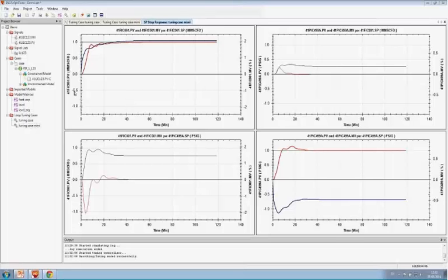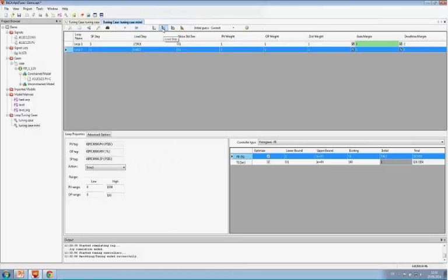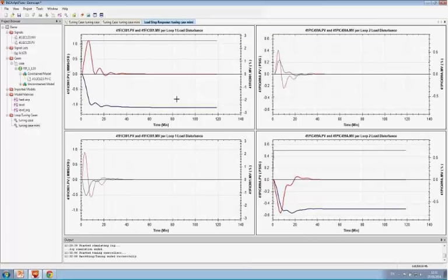If we take the flow as an example, here we see the response of the flow to a set point change, and in this plot horizontally to the right you will see the pressure reacting to that. So also in the MIMO case we can look at how these controllers respond to a load change, which you can judge here.